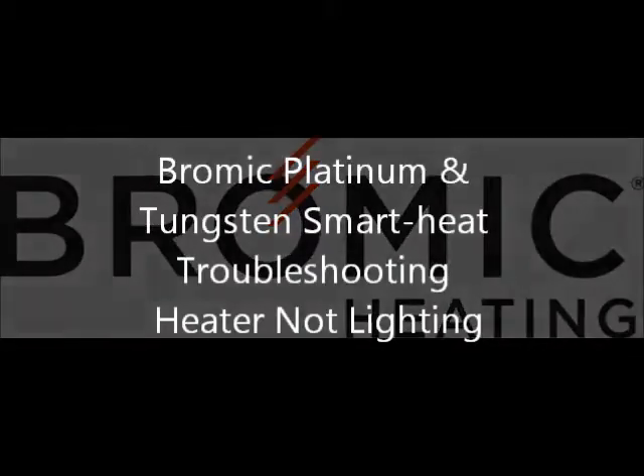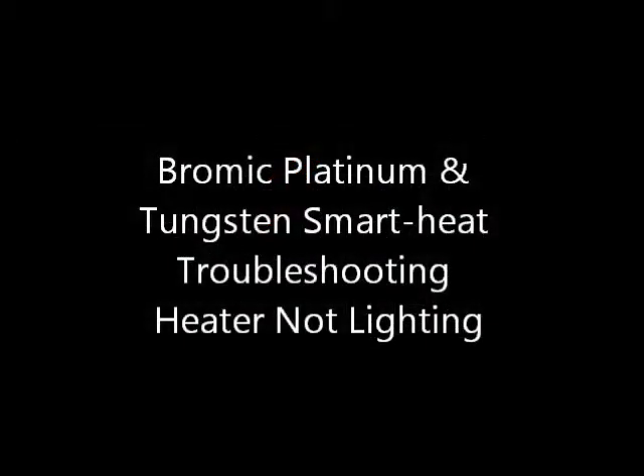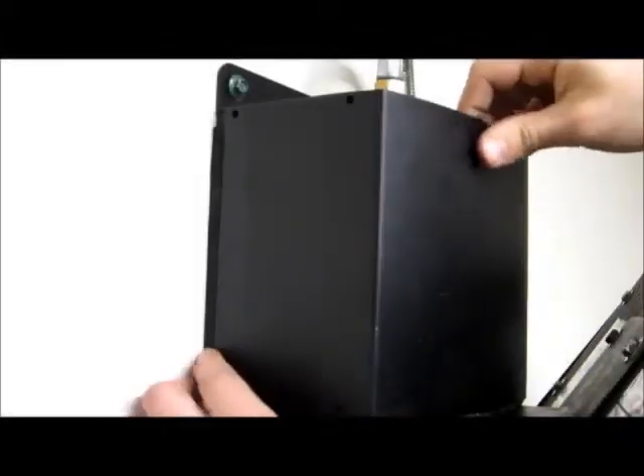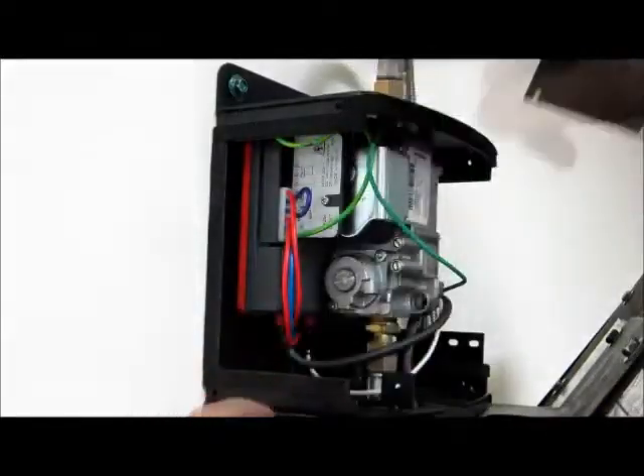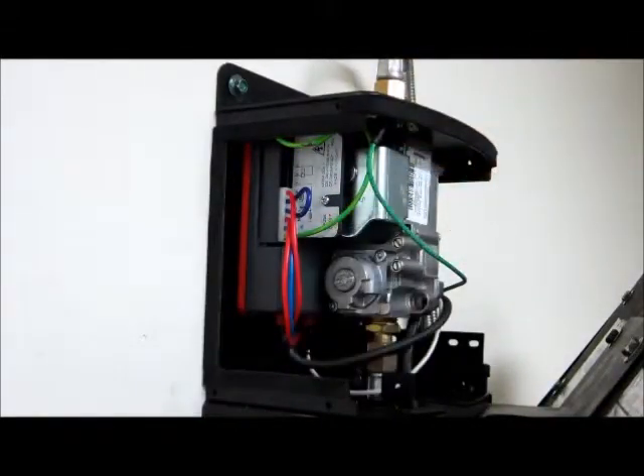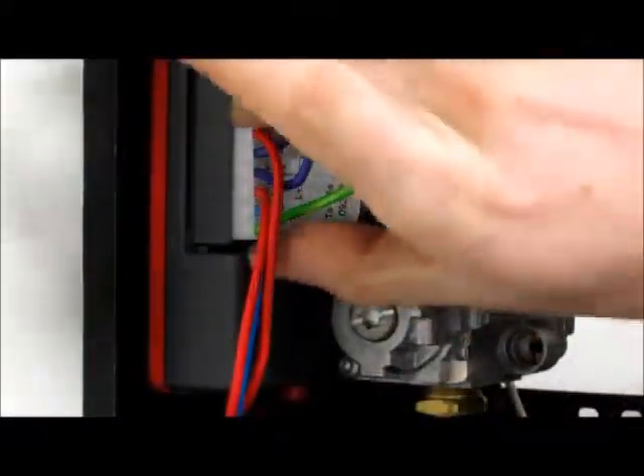If a newly installed tungsten or platinum heater is not successfully lighting, following these troubleshooting steps may assist you in isolating and rectifying the issue. Remove the control box cover. If the unit is not sparking at all, ensure that the wiring harness plug is plugged in correctly. The plug must occupy the bottom 6 terminal pins.